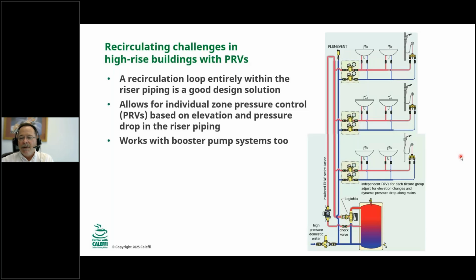We have our supply water coming in here. Here's a pressure reducing valve to reduce from the street pressure down to the system. We're showing a tank here, as I mentioned too. This could be tankless or heat pump water heater, doesn't matter. We're showing a digital master mixing valve here, but the important thing is, look at the recirc loop. It's running on the high pressure side of the PRVs in the building.